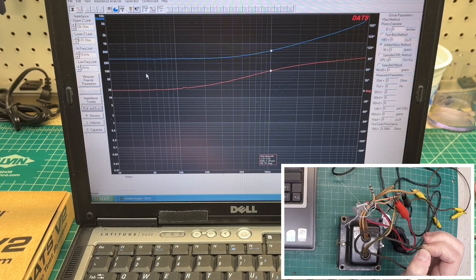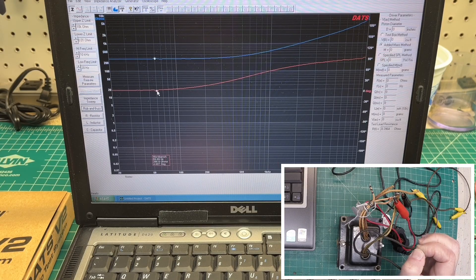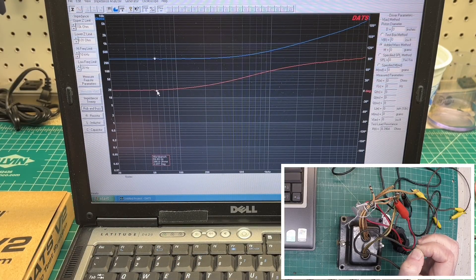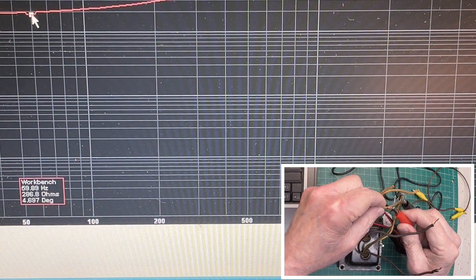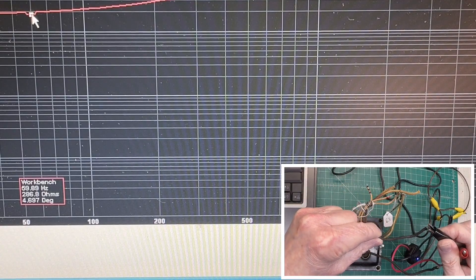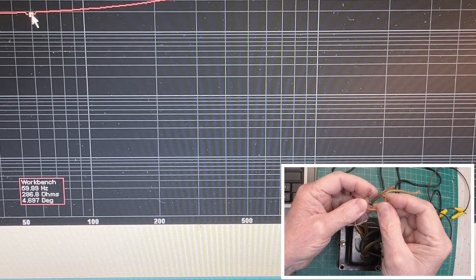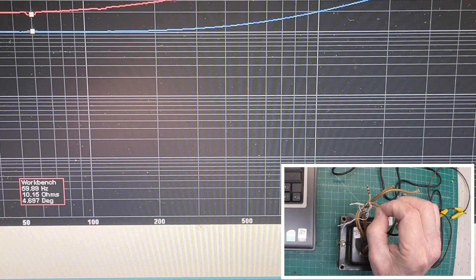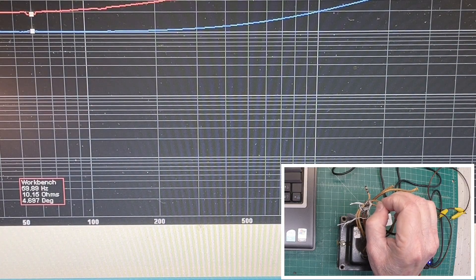I'll do some quick math. I'll go here to impedance sweep, and I'm going to move my marker down to around 60 hertz or so. That may be hard to see, but I'm going to take note of the ohms — let me see if I can zoom in. Now I'm going to reverse the leads and go to the primary side. I'm going to take my high voltage winding, short it, and just repeat the test, and take note again of the impedance — 10.15 ohms.